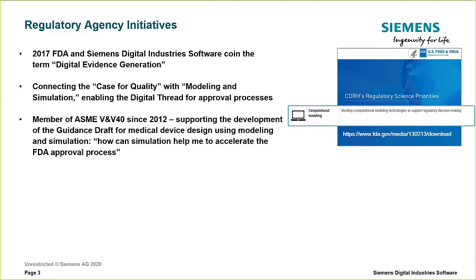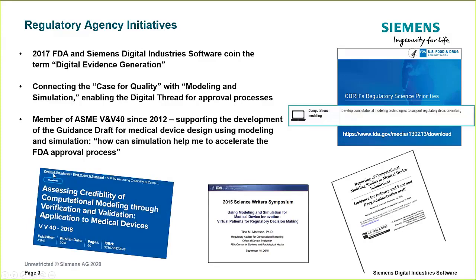Siemens has also been involved with the FDA's Case for Quality program, which seeks to go beyond just compliance and focus on critical-to-quality practices that result in higher-quality outcomes. Siemens has been a member of ASME V&V 40 since 2012, with the goal of helping answer: how can simulation help a device developer accelerate the regulatory process? There are many publicly accessible documents from FDA, ASME, and others that outline these efforts.